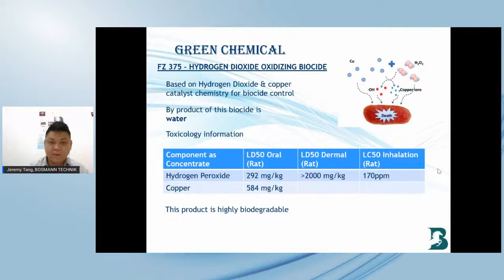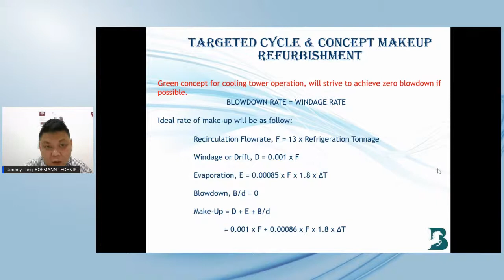Okay, we've finished the green chemical introduction, so let's move to the second topic. To make sure the cooling tower runs optimally, we need to target the cycle makeup. Based on the green concept of cooling water tower operation, we strive to achieve zero blowdown if possible, so the blowdown rate equals the windage rate. The ideal makeup water follows this formulation.